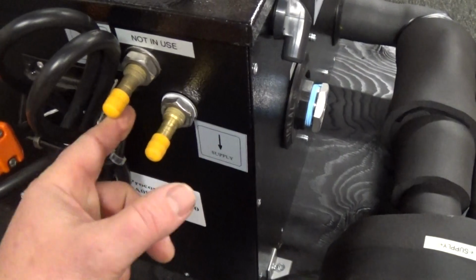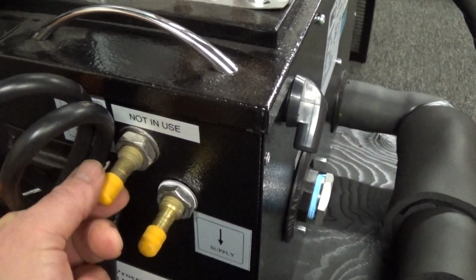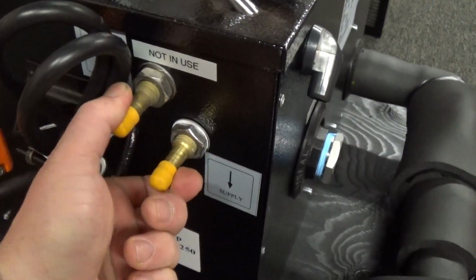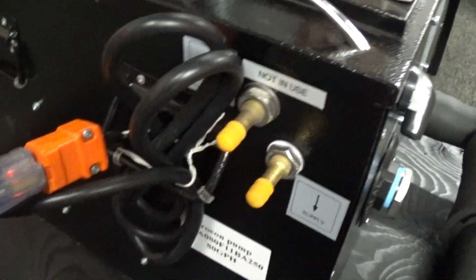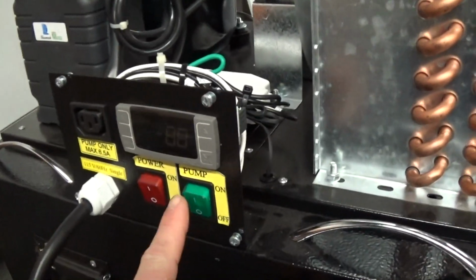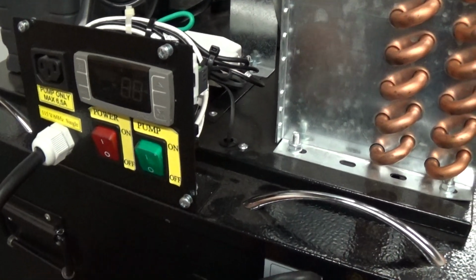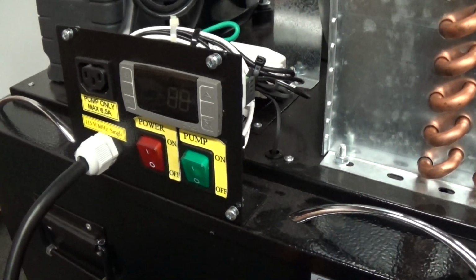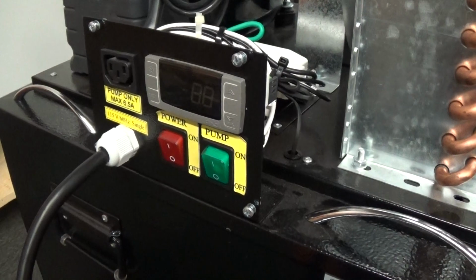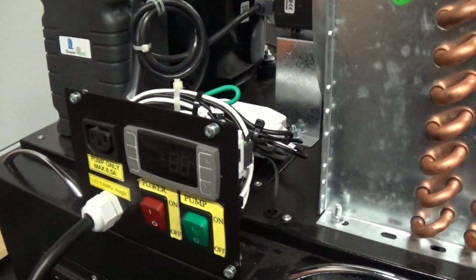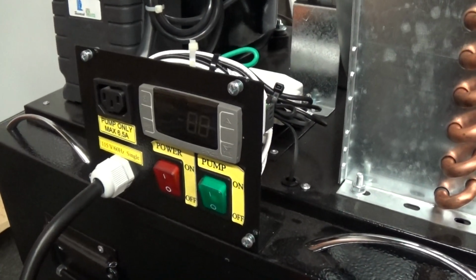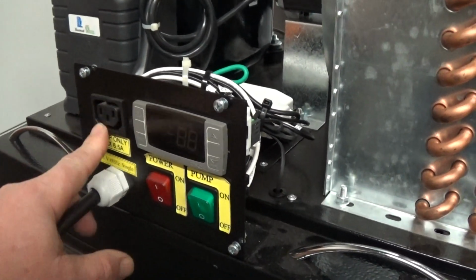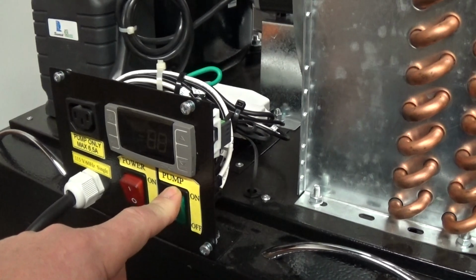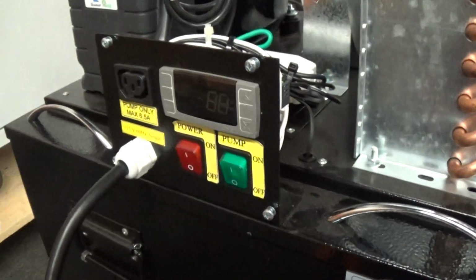These lines here are not in use. That's from the prior smaller pump that was on there. And this pump button here is no longer active. That was for the original smaller pump that we removed and put in place this bigger, heftier half horsepower glycol reservoir. Similarly, this plug you're not going to use, and this pump button's not used. You simply plug this in and it runs all the time.